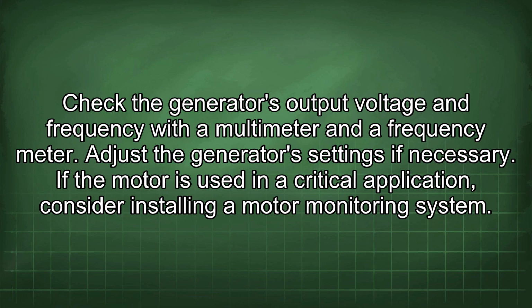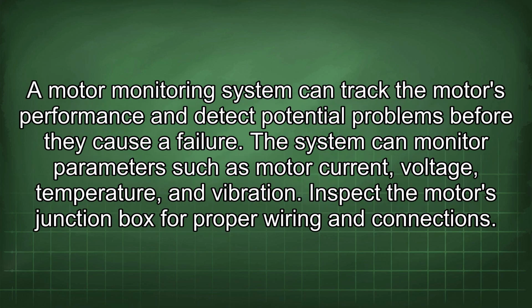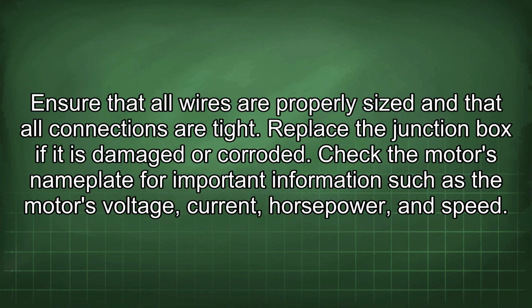If the motor is used in a critical application, consider installing a motor monitoring system. A motor monitoring system can track the motor's performance and detect potential problems before they cause a failure. The system can monitor parameters such as motor current, voltage, temperature, and vibration. Inspect the motor's junction box for proper wiring and connections. Ensure that all wires are properly sized and that all connections are tight. Replace the junction box if it is damaged or corroded.